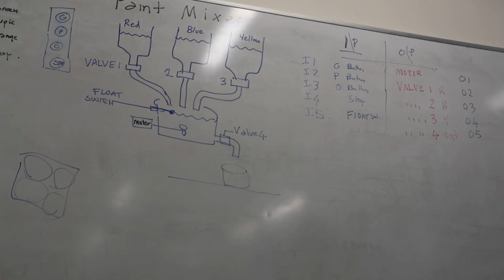Those other two are sets and resets. We try not to use those because when we set it, it'll stay on forever until it gets a reset. So if I wanted to use the momentary switch, I should use this one, and we'll put our own latch in it there. When that comes on, the only problem is this is going to run forever.